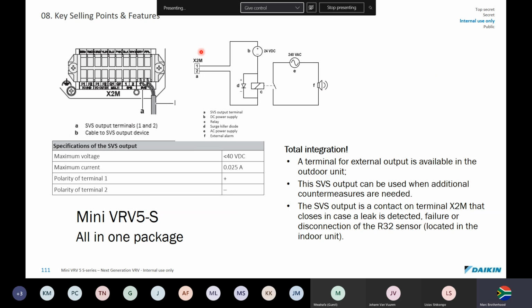This is one of the outputs that are available that I was telling you about earlier. The SVS output terminal: at maximum voltage, you can put out 40 volts DC. So a terminal for external output is available in the outdoor units. This SVS output can be used when additional countermeasures are required, like maybe a coil or something. The SVS output is connected on terminal X2M. So what we're pretty much telling you is, we can give you a 40 volts DC output.